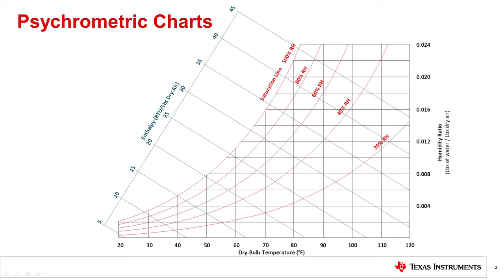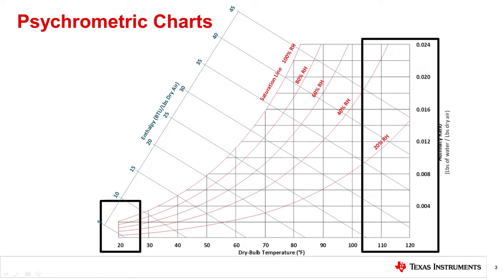Looking at the whole chart, you may also notice that the relationship between the amount of water vapor that ambient air can hold and the air temperature is exponential. In other words, at very low temperatures, the amount of water vapor that could be contained in air is extremely small. This makes the relative humidity curves, shown in red on this chart, much closer at low temperatures and much more spread at higher temperatures. This compression makes it difficult for many humidity sensors to work well at low temperature.